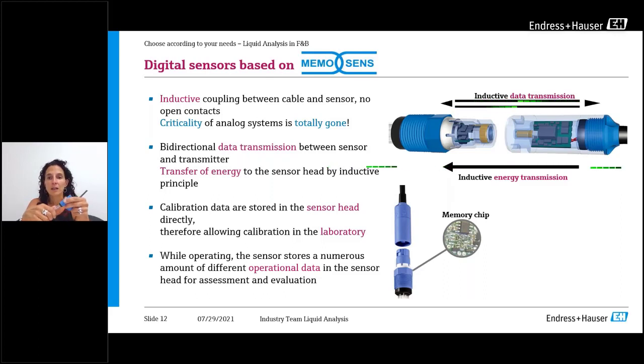So what Endress+Hauser did a long time ago was to create this MemoSense protocol. And what it does is that on the side of the sensor, I'm measuring in millivolts, and then the signal is transformed to a digital value, and then it's transmitted through the cable, so now I don't need a special cable, it's just a digital cable, and then it goes to a transmitter. This allows the installation to be completely independent of the measuring point. So what I need to calibrate is just the sensor, because the whole rest is digital.